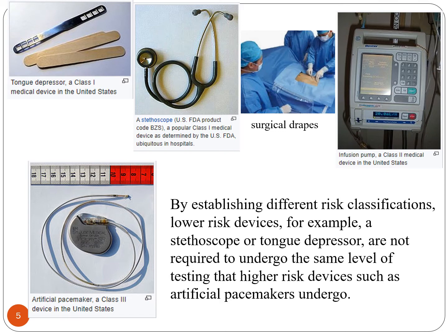Surgical drapes and dressings for surgical operations are class 2, due to the potential for risk if there is a misuse or a mistake. Also the infusion pump, which allows a very low infusion rate or tightly controls the infusion rate of fluids through IV infusion, is considered a class 2 medical device in the United States.